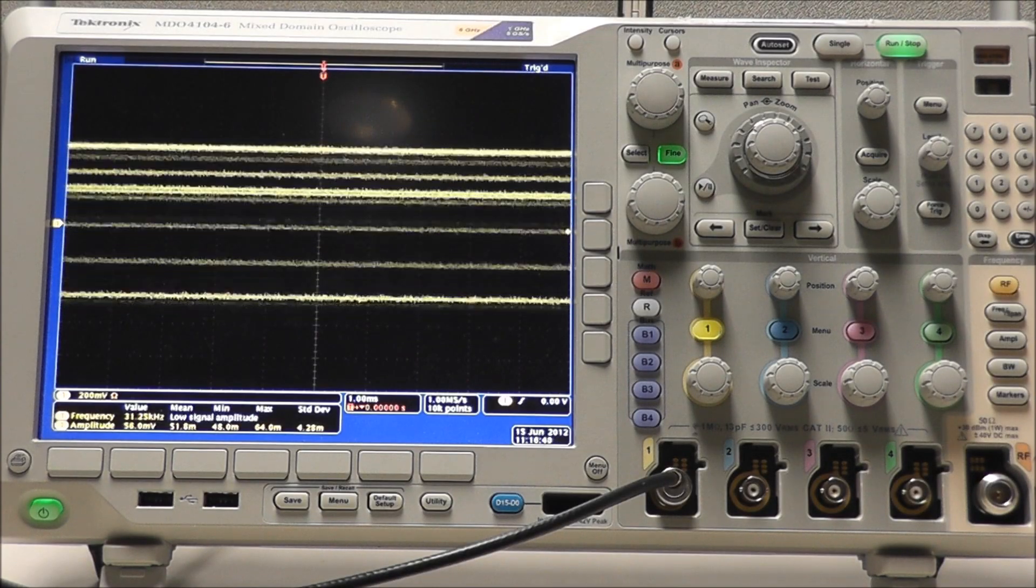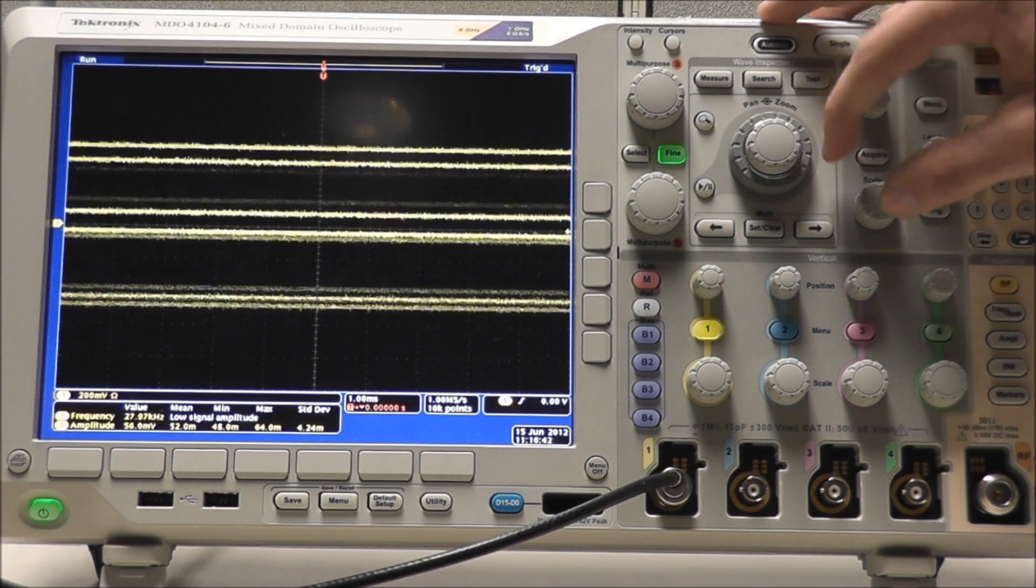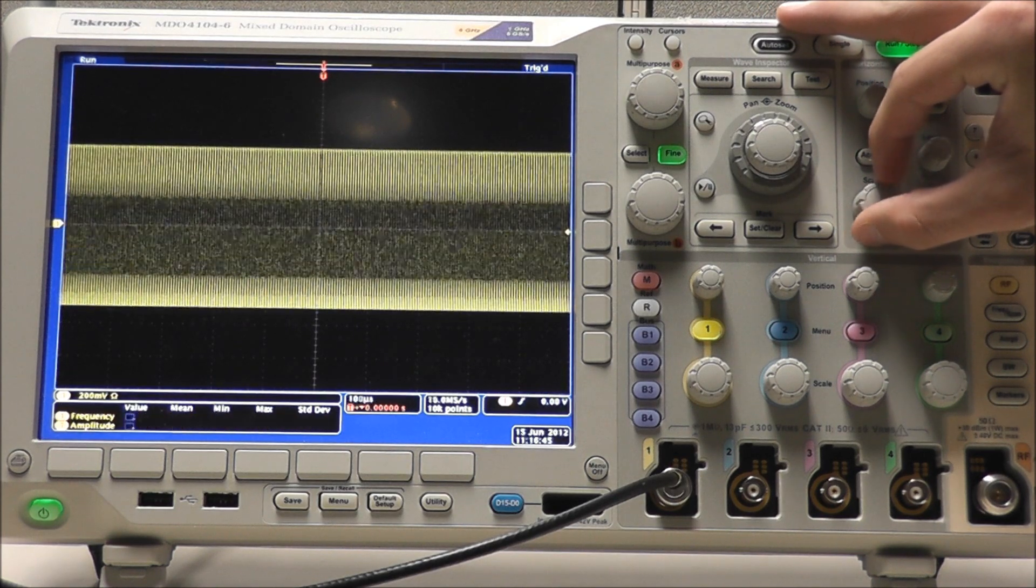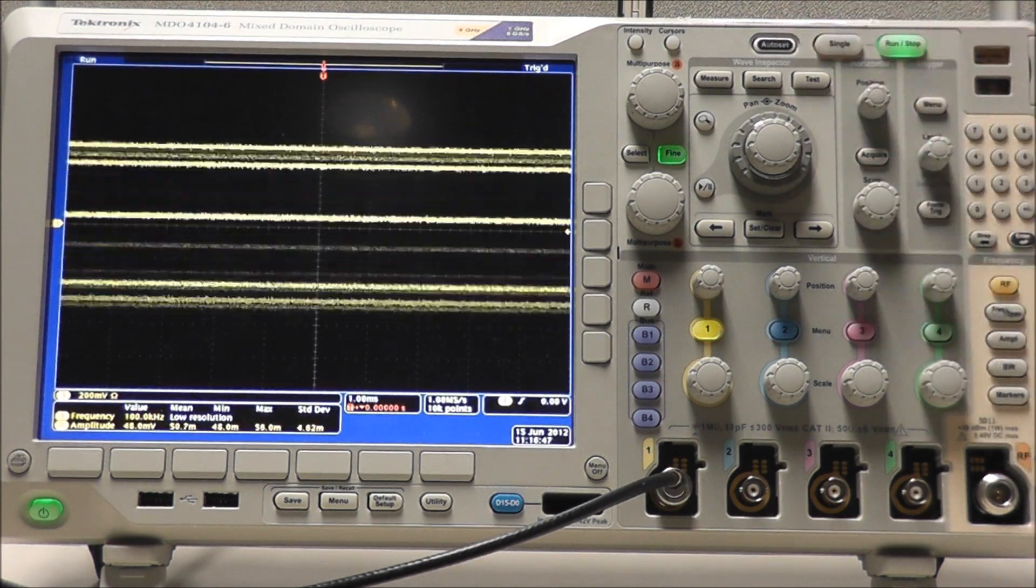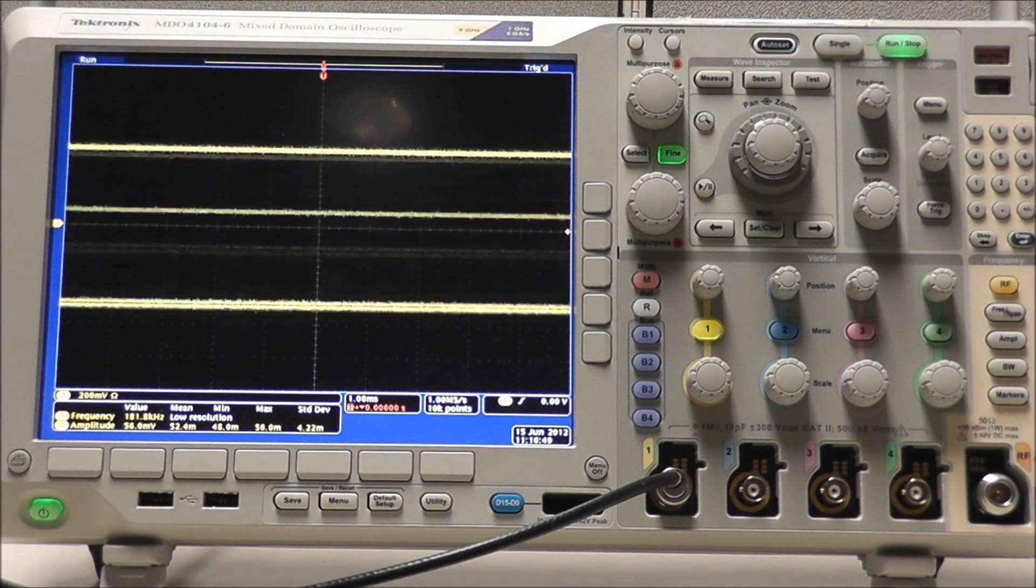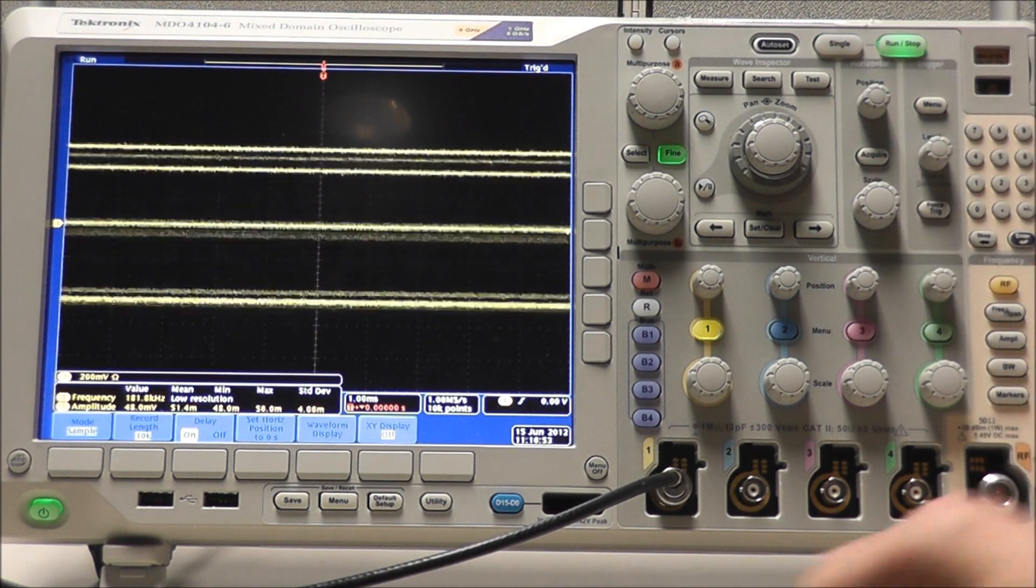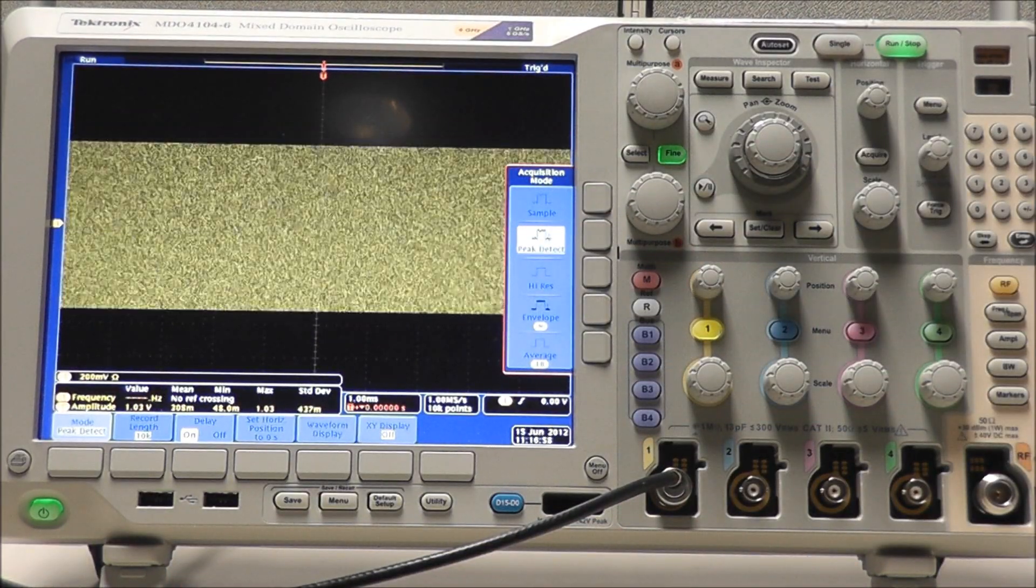There are a couple of ways to check for aliasing. We can perform a horizontal test using the horizontal knob to change the horizontal scale. If the shape of the waveform changes drastically like we see here, we may have aliasing. Or we could perform a peak detect test by selecting acquire, mode, then peak detect. Again, if the waveform changes drastically, we may have aliasing.